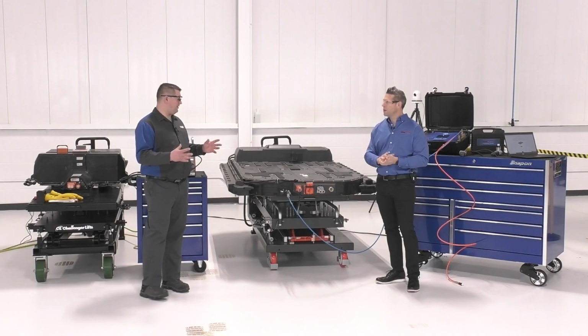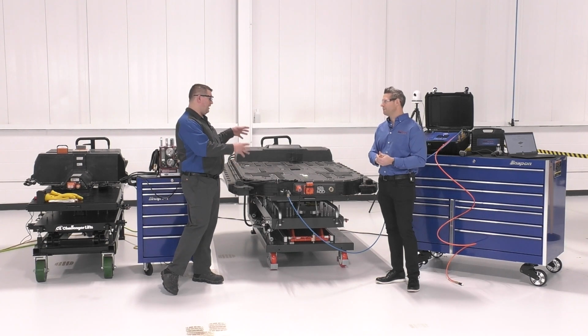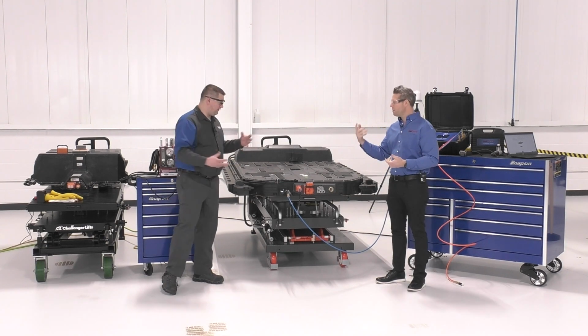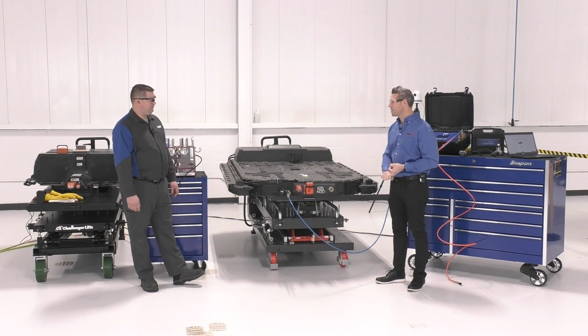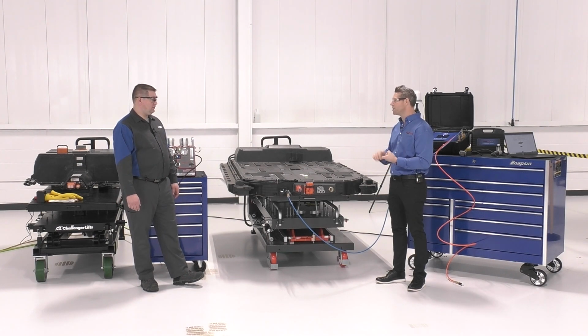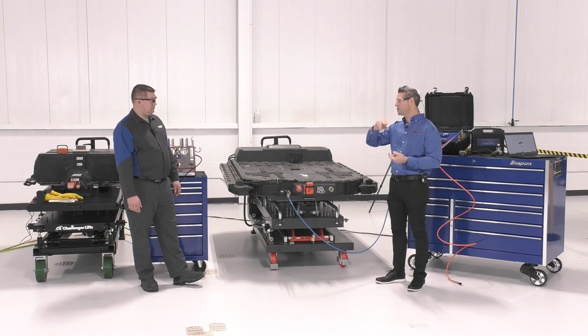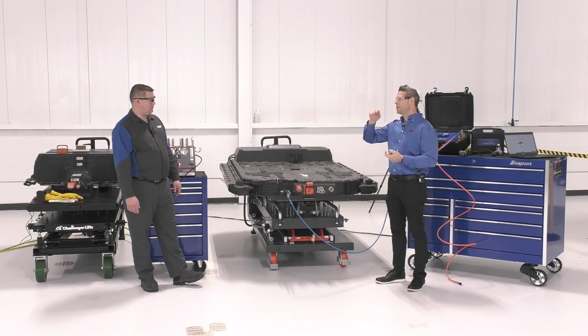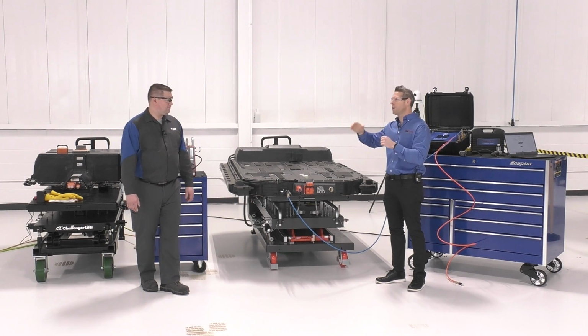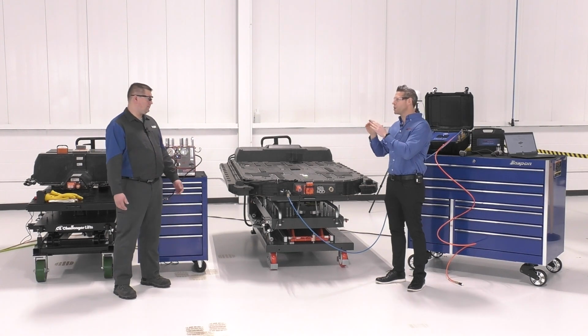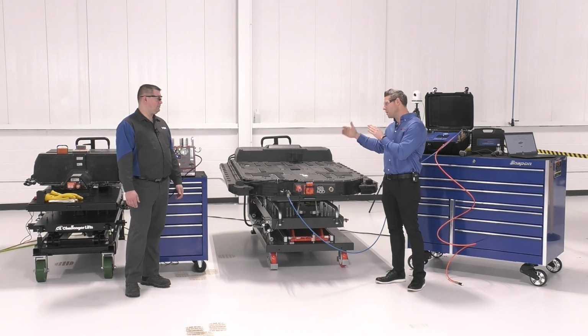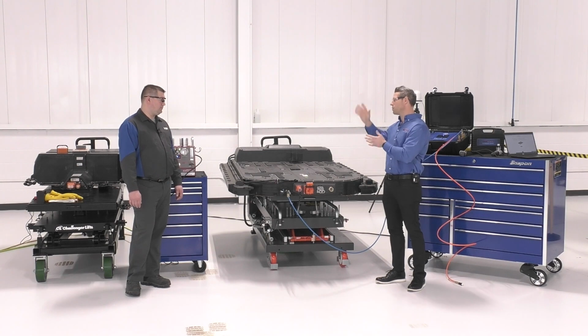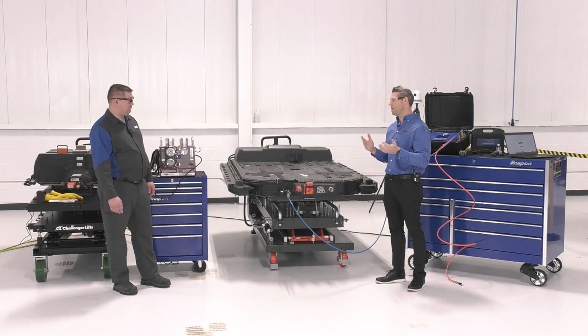But in general, it really ranges all over the place, because it's going to depend on the size of the battery enclosure itself, how much internal volume there is, the type of battery, what the specification is, how it's designed, and what the OEM decides needs to be done. Some batteries take more stabilization time, so you get this little hysteresis that goes on, and you need a bit longer stabilization. Other batteries you can do a shorter stabilization, a shorter test on the pressure drop or the vacuum rise, whatever test you're using. So it varies all over the place.